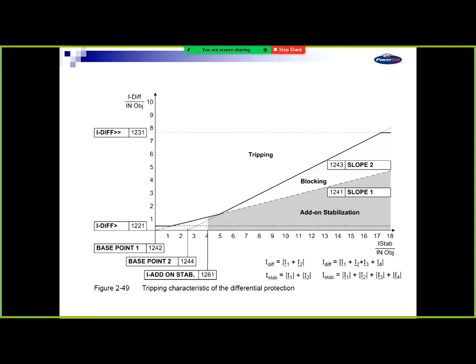And the bottom little bit there for IDIF is like, that's where you may have tap change. If you have a look and you've got a big variation in your voltage on one side because of a tap changer, you'll have different currents flowing, but it's still stable. So for a 100 MVA transformer that's got 100 MVA in it, the current flowing when you're on bottom tap to top tap is quite a big difference. It's just normal, balanced operation. You need to account for that.